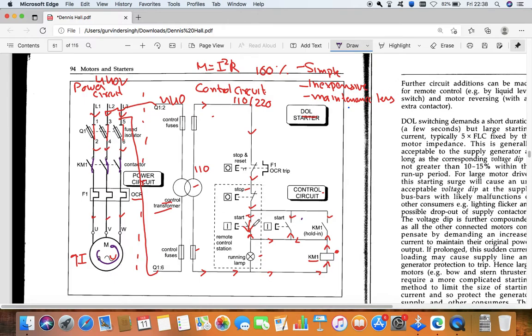Okay, now you release this switch and it will come back and open again. When it opens again, you can see this relay will de-energize and it will open this and the motor will stop, but it will not stop because we have something called a hold in contact, or somebody says retaining contact. This is KM1. So what will happen when you press this switch? This KM1 relay energizes this contactor and also this contact. Now when you release, it will open up and the supply, instead of going from here, is going from here. Okay, so the circuit is completed like this, so the motor will keep on running.